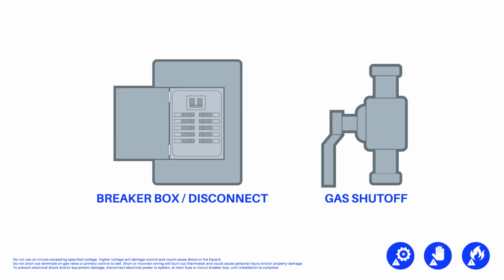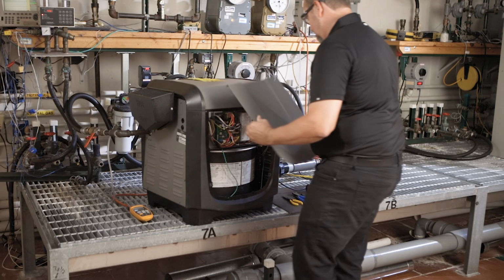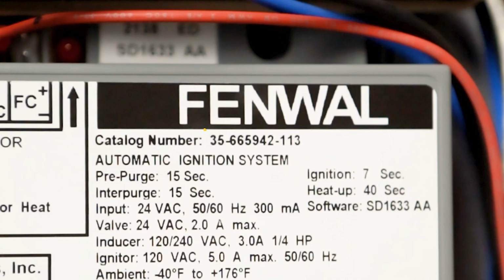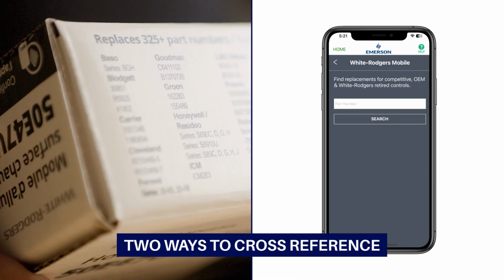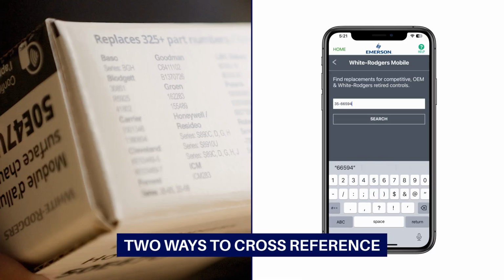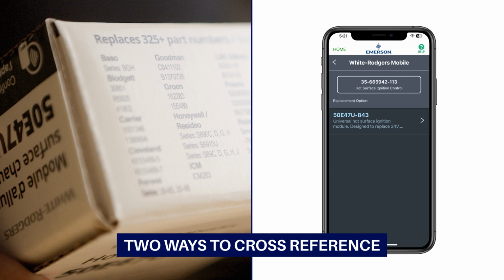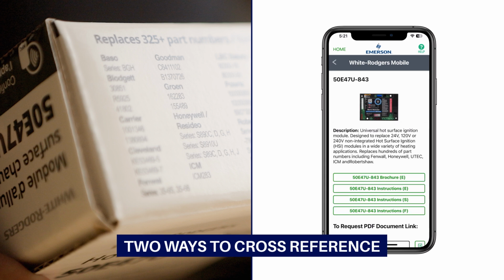First, ensure power and gas are disconnected prior to servicing the unit. Remove the access panel. Check the part number on the existing control and verify it is one of the 325-plus modules that can be replaced with the 50E47U-843. The carton contains the most popular cross-references, but for a complete list, use the White-Rodgers mobile app.